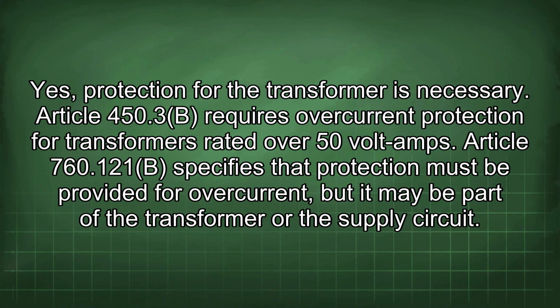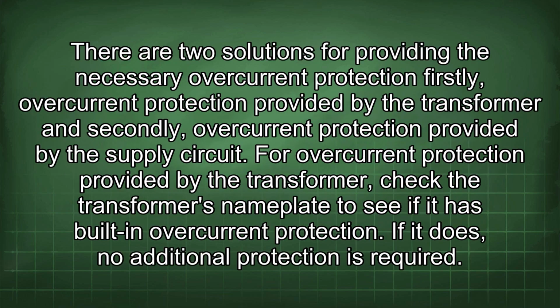Yes, protection for the transformer is necessary. Article 450.3b requires overcurrent protection for transformers rated over 50 volt amps. Article 760.121b specifies that protection must be provided for overcurrent, but it may be part of the transformer or the supply circuit. There are two solutions for providing the necessary overcurrent protection. Firstly, overcurrent protection provided by the transformer, and secondly, overcurrent protection provided by the supply circuit.